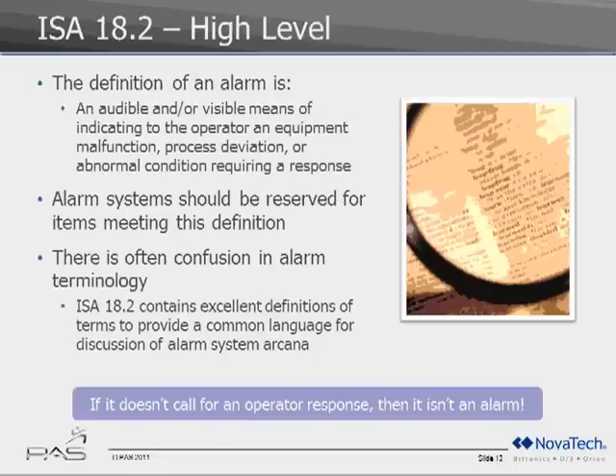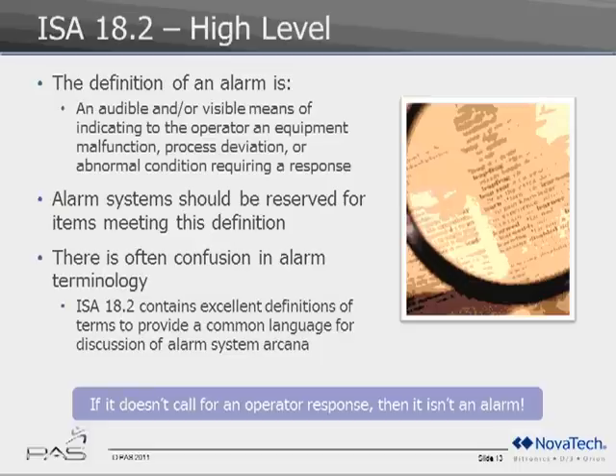Looking at what an alarm actually is — a lot of work in 18.2 was done to carefully craft that definition. An alarm is an audible or visible means of indicating to an operator an equipment malfunction, process deviation, or abnormal condition, and the key is that it requires a response. Many legacy alarms were really informational messages not requiring a response. Here, alarms are specifically defined as requiring an operator response.